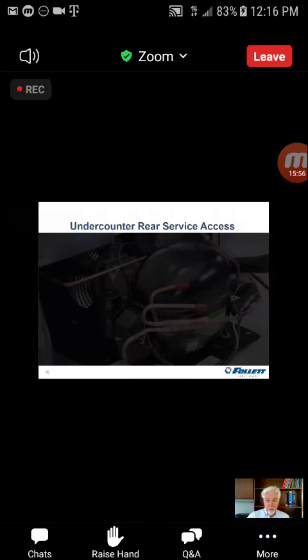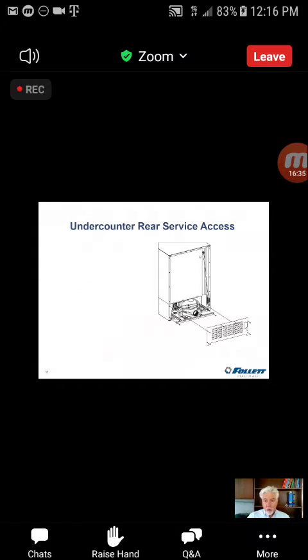Something I would like to mention about that first step when we're removing the front panel and that little side plate there, that baffle that's in there, is a critical component, because it prevents recirculation of the air coming off the condenser, and it prevents a return to the low pressure area in the front where the air goes through a second, third, and fourth time. So it's that baffling in there that enables this unit to totally front breathe. It does not require any top, side, or back clearance whatsoever, as long as that baffle is in place. Now, if that's not in place, then we're going to get recirculation, which is going to drive head pressures up in the refrigeration system.